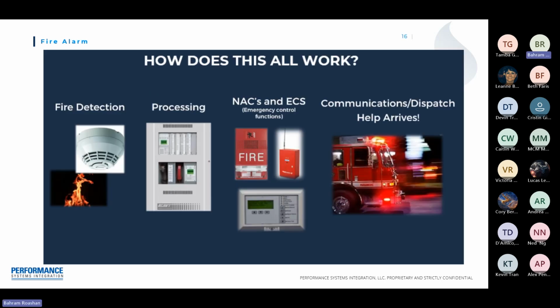How does this all work together? Well, these systems are designed with intricate engineering. Fire alarm systems work by detecting an input, such as a fire or other threat, sending an output signal, activating the horn strobes to go off, elevators to be recalled, and the HVAC system to shut down. The fire alarm control panel then sends a signal via a phone line, cellular tower, or radio network to a central station. The central station then dispatches the local fire department with the signal they received. After the fire department is reached, the central station operator will contact the responsible party.